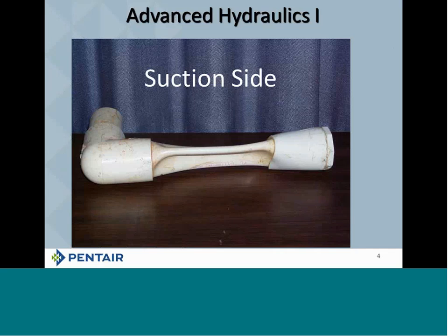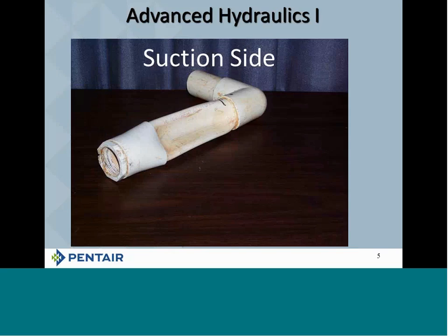When the temperature of the water got the melting point of the plastic soft enough, because we are creating a vacuum on the suction side, you can see we collapsed that pipe. And when you collapse that pipe, you're not going to get much water to come through there. And so that's why it's very important that we understand what's taking place when we deadhead a pump.